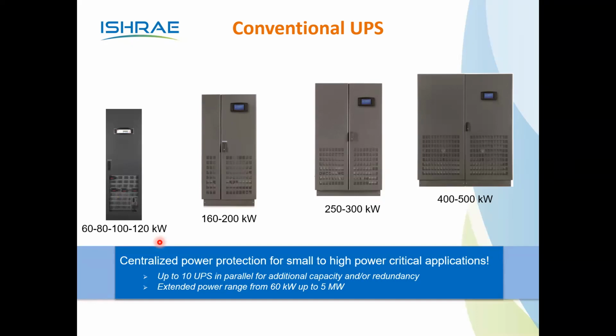Now, this is the latest technology in conventional UPS systems. We need to ask what the output power factor of the UPS system is, not the input power factor. If the output power factor is unity, that's a better technology, because now most IT loads are designed for a unity power factor. Two decades back, yes, the loads were designed for 0.8, so absolutely not a problem. Now all the loads are designed for a better power factor, 0.9 plus. And why do we need to degrade on this? So let us move towards a better technology, that's a unity output power factor.